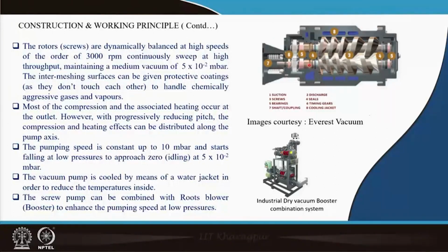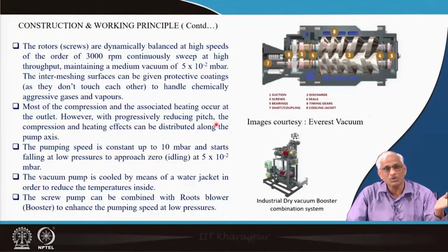So 5 into 10 power minus 2 millibar is a good enough pressure, good enough vacuum for most applications. So you can achieve good vacuum and also huge pumping speed - a beautiful combination of both. That is very important. So whatever heating effects occur in various compression zones, you have to take care of that, as I already told you.